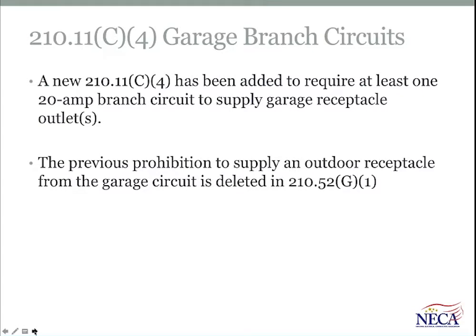Section 210.11(C)(4) is a new subdivision added to require at least one 20-ampere branch circuit to supply garage receptacle outlets. Prior to this addition of the code, you could supply your garage in a dwelling unit with a 15 ampere general purpose branch circuit. You didn't have any specific requirements, but there's a lot of capacity needs these days, and Panel 2 recognizes additional tools and the requirements for tools and things that go on within a residential garage that really prompted this new requirement. Also, you'll see within this area of the code and a related provision, the restriction to supply an outdoor receptacle from the garage circuit in 210.52(G)(1) was deleted.